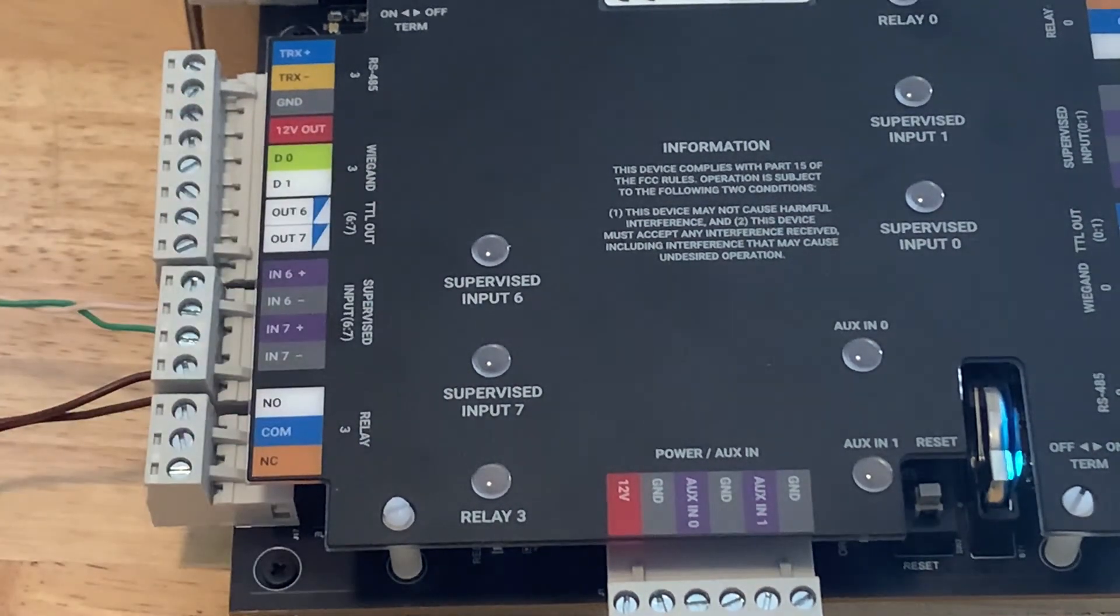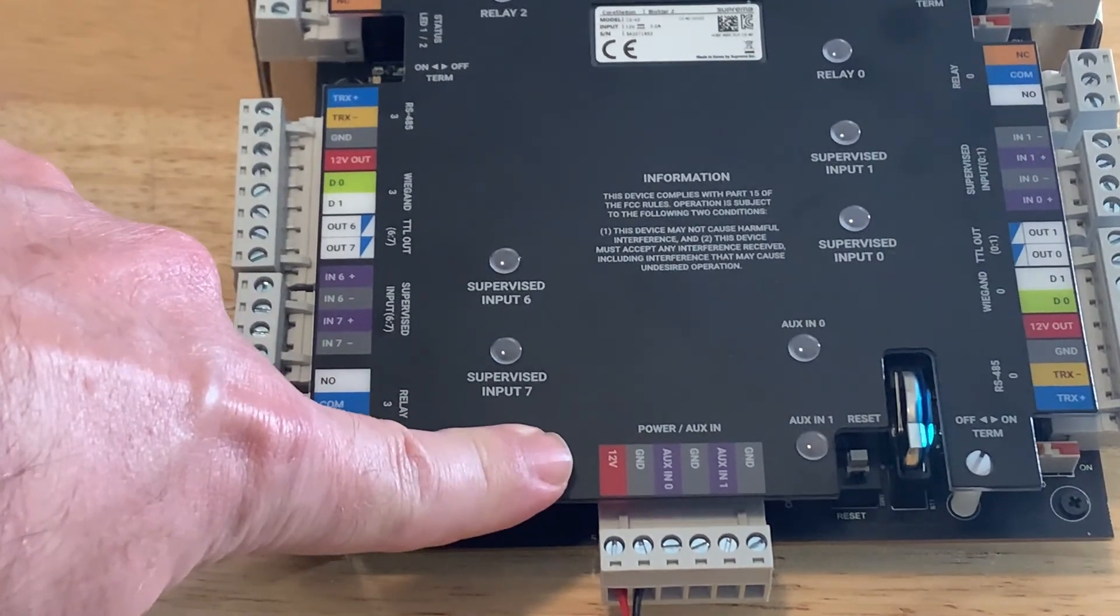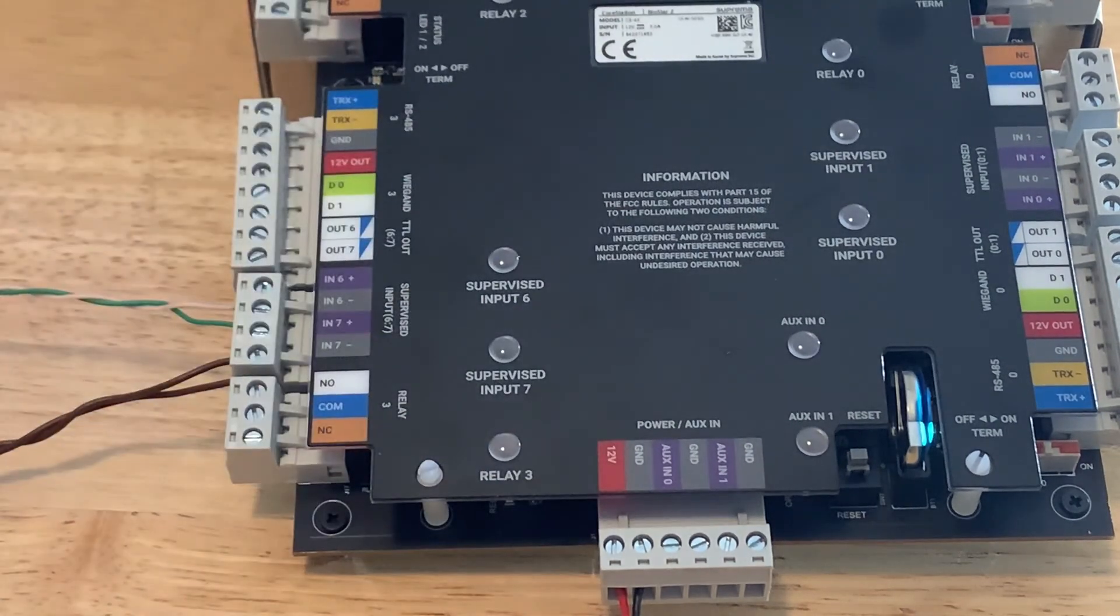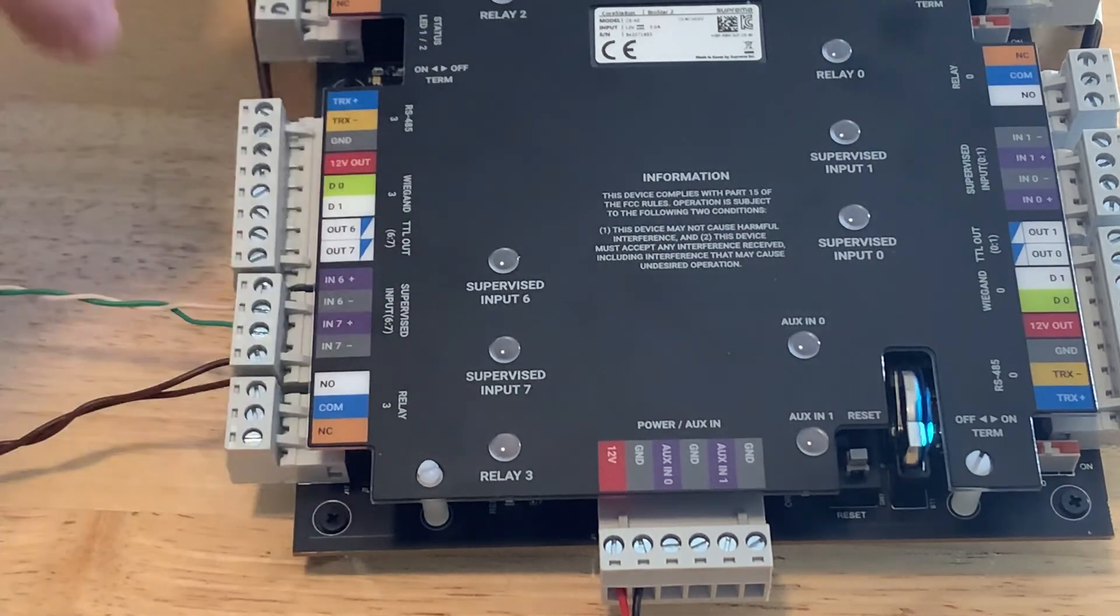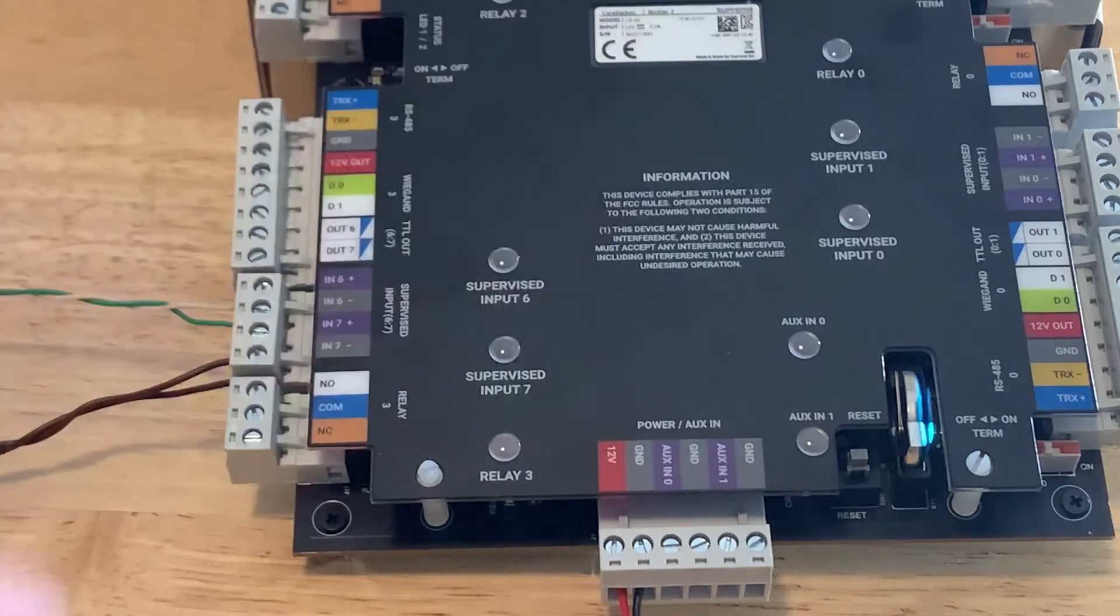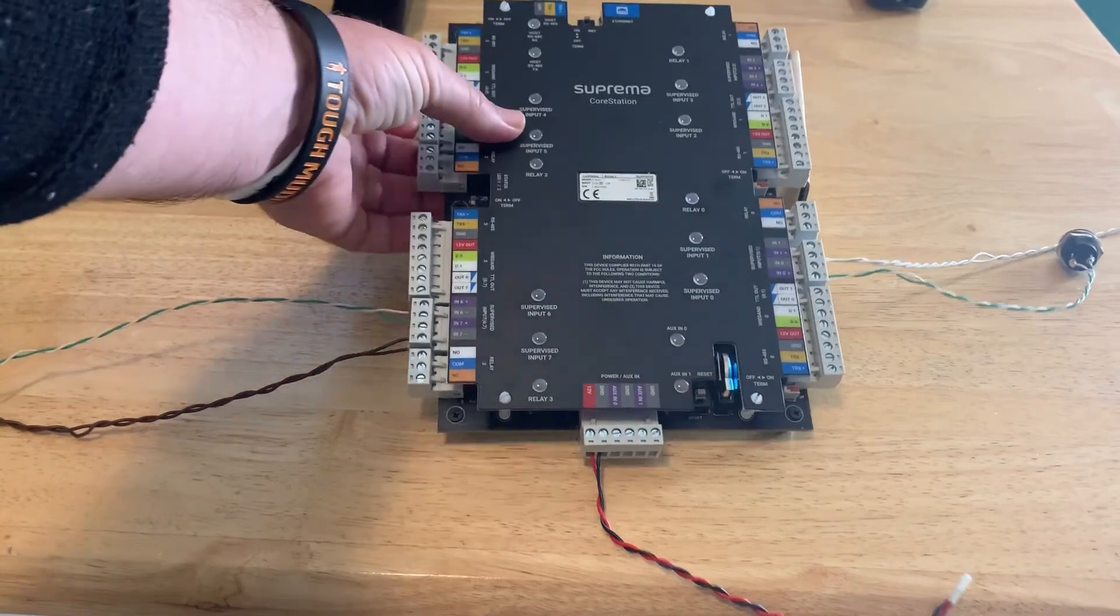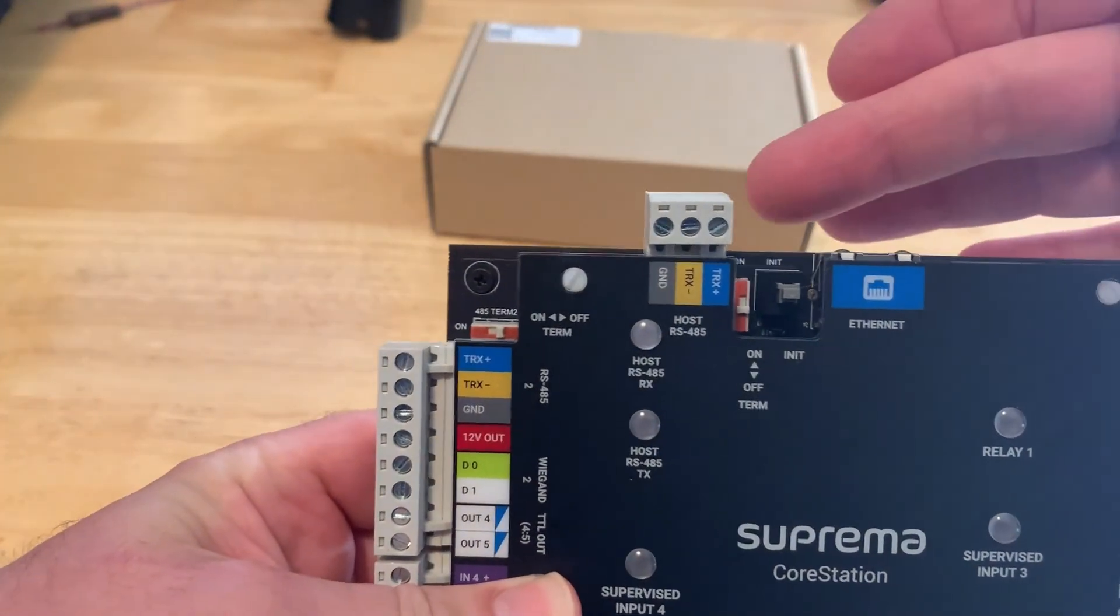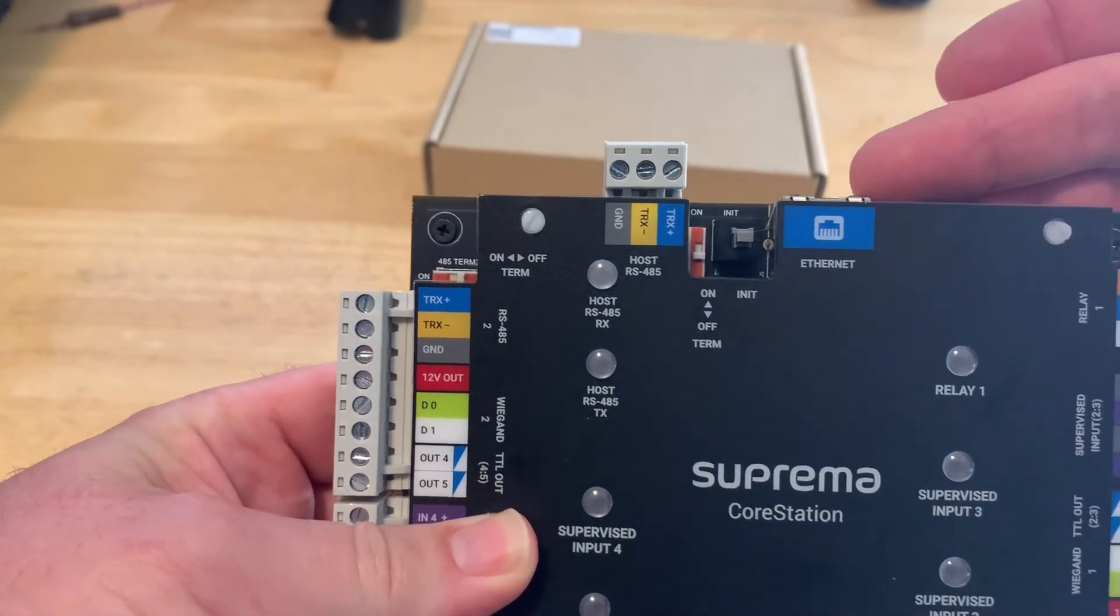Now also on the board here at the bottom we have the 12 volts DC coming into the unit as well as a couple of auxiliary inputs which you could wire a cabinet tamper to. Each door port is here and you have four 485 connections on the board, and at the very top we have another 485 connection which is called the host connection and then the ethernet connection when connected to the LAN.